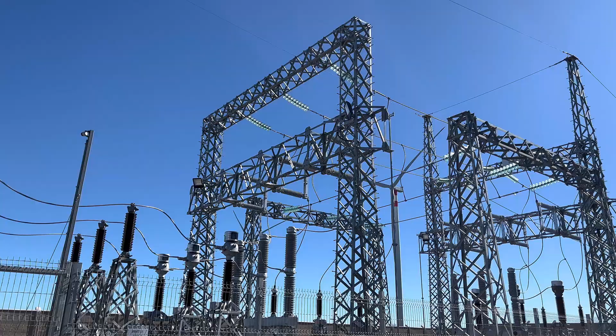A protection relay is a sentinel. Its job is to watch the electrical conditions on the lines it monitors, and if those conditions exceed a set threshold, disconnect the line before damage can spread. Think of it as a circuit breaker scaled up to industrial voltage, governed by a set of parameters an engineer enters by hand. When those parameters are correct, the relay is one of the things that keeps a grid stable. When they are wrong, the relay becomes a fuse set to blow at the wrong moment.